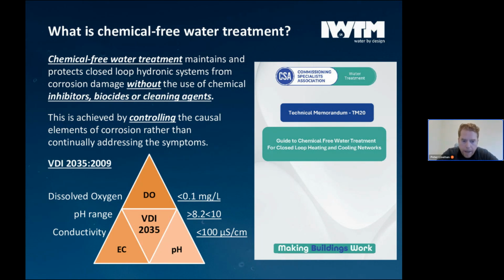You want your pH of the water to be between 8.2 and 10. And you want that because the majority of bacteria can't survive within that pH level. And a pH between 8.2 and 10 is a good pH for most metals. So holistically, VDI has thought about what is good for the majority of the system. And conductivity.